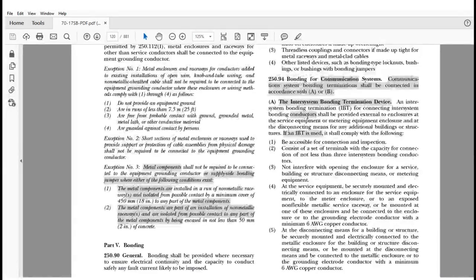And so here's what they did. They changed it and added to make sure that it was clear, because everybody was wrong when they said you could use that little device to do this. So they made it really clear for people to understand. It says communication systems. Okay? Communication systems bonding terminals shall be connected in accordance with A or B. All right, what does that mean, A or B? Well, A tells us it's the intersystem bonding terminal. It's specifically devoted, now called the IBT, for interconnecting conductors or bonding conductors dealing with the communication systems. And it covers all that information here.